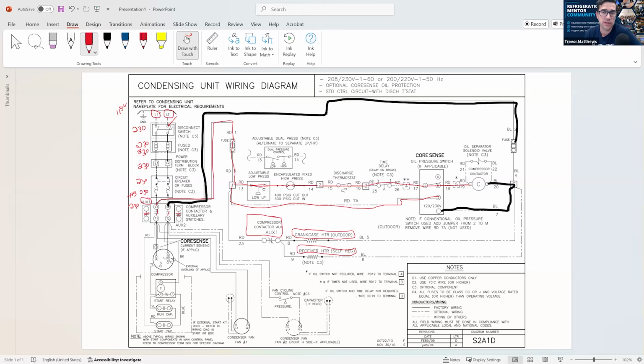Okay, and you need enough voltage. I'm sure in the manual it's going to say like maybe it's 20%. If you have less than 10 or 20%, that it's not enough to pull in the contactor coil. So if you ever heard a contactor coil pulling in and out, in and out, in and out, you might not have enough voltage. There's a voltage drop. There could be a loose wire as well. This stuff here is really, really important to do on systems that are working properly.